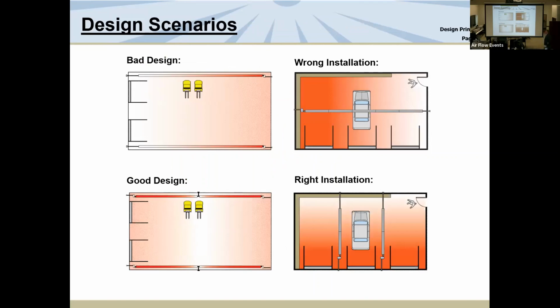So some good design practices are here. All right, this application up there really happened. The heaters were actually designed by the engineer to have the burners down on that corner. But when the contractor got to the job site, where did he find the gas lines? On the other side. So he put the burners down where the gas is, which is very common in our industry, go where the gas is closest. And then he turns on the heaters, and where all the load was down by the overhead doors had no heat. So how did we fix it? Instead of ripping out the system, we simply broke the system in the middle, added burners on the corner. We didn't add any more pipe. We didn't add any more BTUs. We just balanced the load, okay? Balancing the load is key.